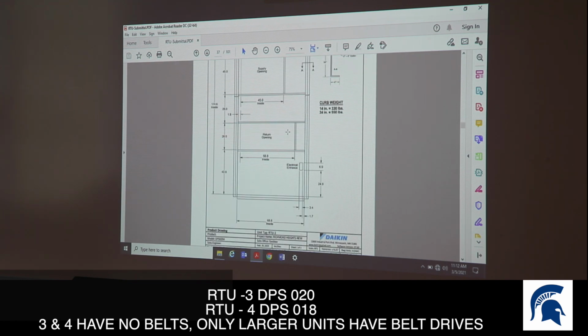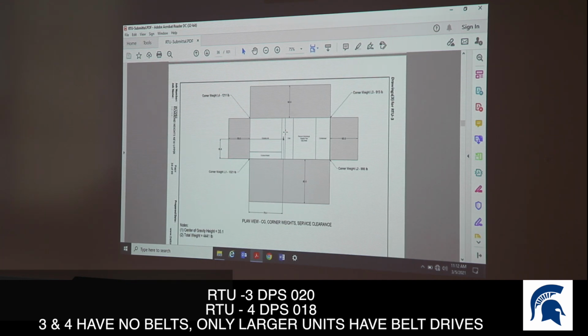And when we get upstairs, if we look at a larger one, we're going to talk a little bit about lubrication, okay? Most of the fan bearings are lubricatable. Not all the motors are. Every motor manufacturer is different. Some come with Zerk fittings, some don't. If they don't have Zerk fittings, they're sealed bearings, okay? If they do, you need to grease them. And they were probably greased at startup, okay?